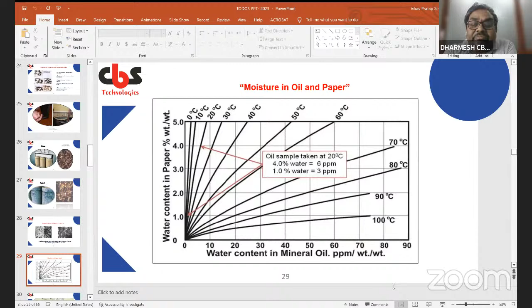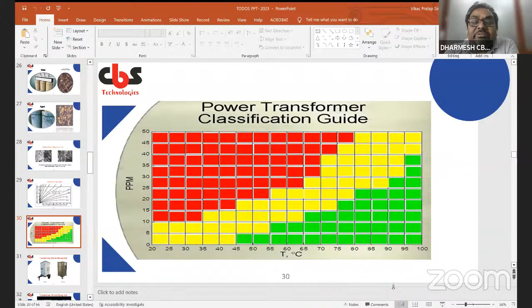This is a power transformer classification guide showing how much ppm is good. The red zone is considered dangerous. The yellow zone is the 'chalta hai' type of thing normally tolerated by power utilities. But the green zone is the recommended part, which should be mandatorily maintained. For example, at 45 degrees, 5 ppm should be maintained. This is how the chart should be maintained in all power utilities — this is an ideal chart. Thanks.